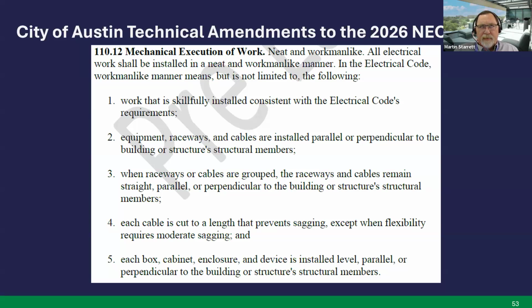In previous electrical ordinances, looping was not allowed, but now it just says that each cable is cut to length, which prevents sagging. Any looping would fall under the particular cable article in the National Electric Code as far as the radius of bend. So it's already covered in the code. Next slide.